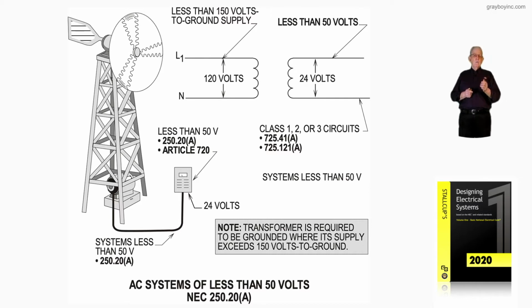But now notice we're less than 50 volts to ground, and we have 24 volts there. Now, as long as we apply 250.20(A)(1), basically, A1 of that section, we would not have to ground that 24 volts. We could run it ungrounded, as you see in the illustration.